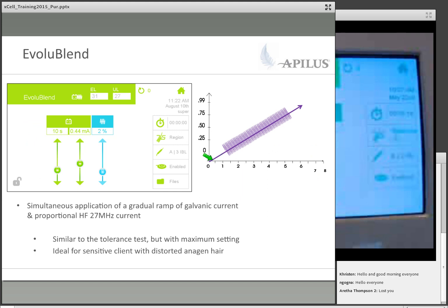EvoluBlend is the only one where the blend does something completely different. So the galvanic here, instead of doing its usual trapezoid shape, actually starts at 0 and just keeps climbing up and up until the end of the pulse. This type of blend is usually for very sensitive clients, because the pulse doesn't reach its max mA, the 0.44, until the very end. So the client really doesn't get the full impact of the intensity until the very end.